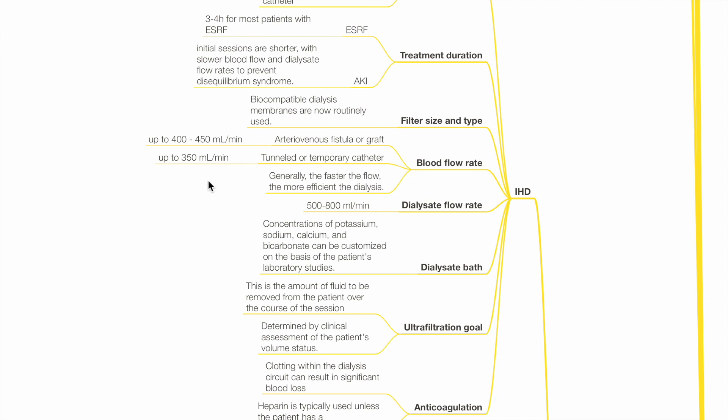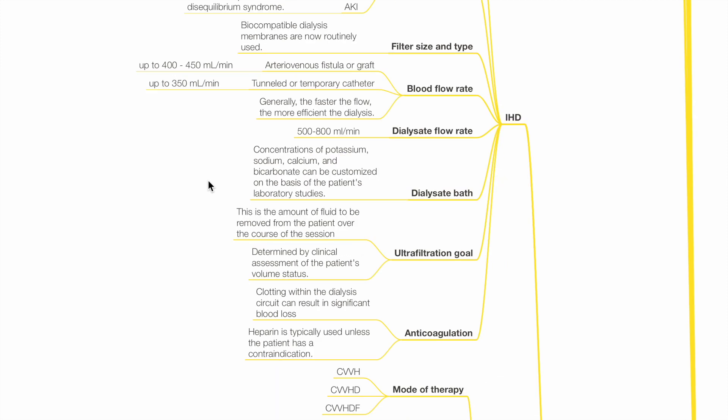Generally, the faster the flow, the more efficient the dialysis. Dialysate flow rate is 500 to 800 mLs per minute.